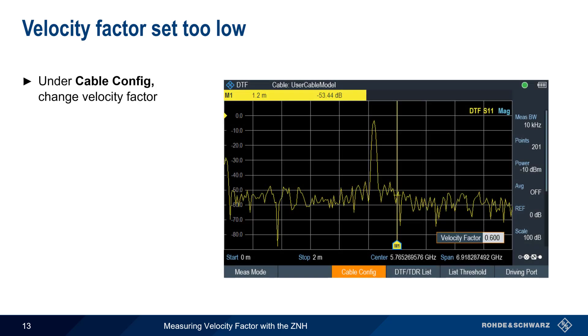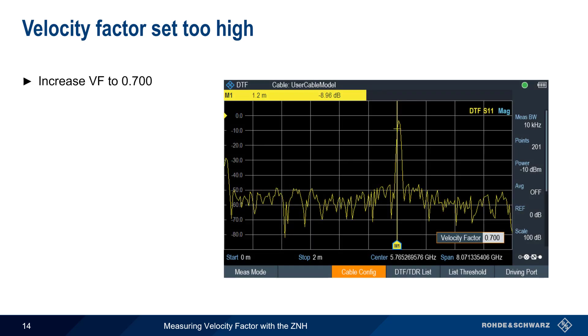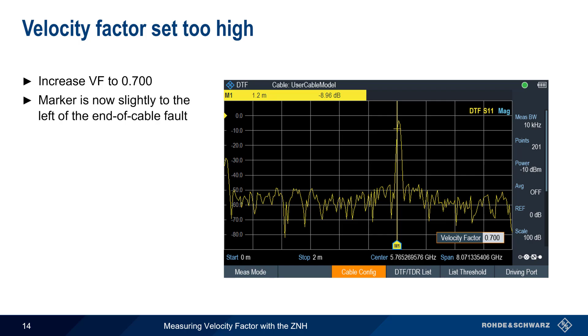Going back to cable config, we start by changing the velocity factor to 0.6. This causes the DTF waveform to move such that our marker is now to the right of the end-of-cable fault, meaning that our manually entered velocity factor of 0.6 is too low for this cable. If we increase velocity factor to 0.7, the marker is now closer to, but also slightly to the left of, the end-of-cable fault, meaning that 0.7 is too high. From this, we know that this cable's velocity factor is between 0.6 and 0.7, and is closer to 0.7.